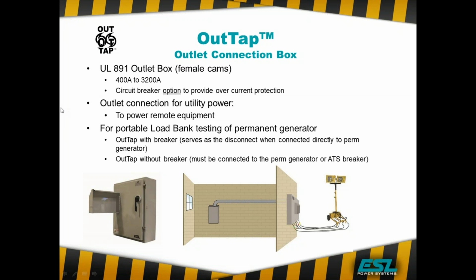The Outtap is then the opposite of a Temp Tap in that it is now outlet power signified with female cams. So somebody can open the enclosure, look at the cams, and know the functionality of that unit. That's why the codes are written that way, so people know whether power is coming out of that unit or power is going into that unit. Again, like the Temp Tap, you can get these with a breaker. They're used quite extensively where you want to power remote devices. A lot of places down there in the Southeast bring in portable chillers in the summertime. And rather than having to bring in a portable generator with it or a chiller with a generator, they can now use the existing facility power, and all they have to do is quick connect in and they're good to go. Sometimes they use them for exterior lighting.